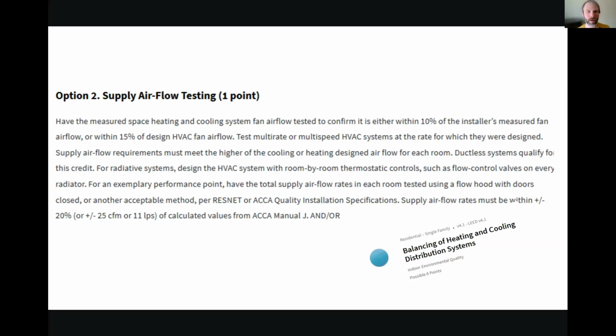And so 3 key things you need to know about this that we're going to go into much more detail is that first, we're looking to get within 10% of the installer's measured air fan flow, which comes on the specs of the system, or 15% of the design HVAC air fan flow, which is usually under the Energy Star for Homes program for LEED. And so we're going to get into these details, but you can also get a bonus point if you're within 20% or plus or minus 25 CFM flow rates if you're using the ACCA standard for the quality installation specifications or the ResNet 310 standard if your rater is doing that verification. Also, you can just throw all that out and do a ducted mini split or a ductless mini split. If it's ducted, it's got to be less than 10 feet of ductwork. And then you don't have to worry about all this stuff.